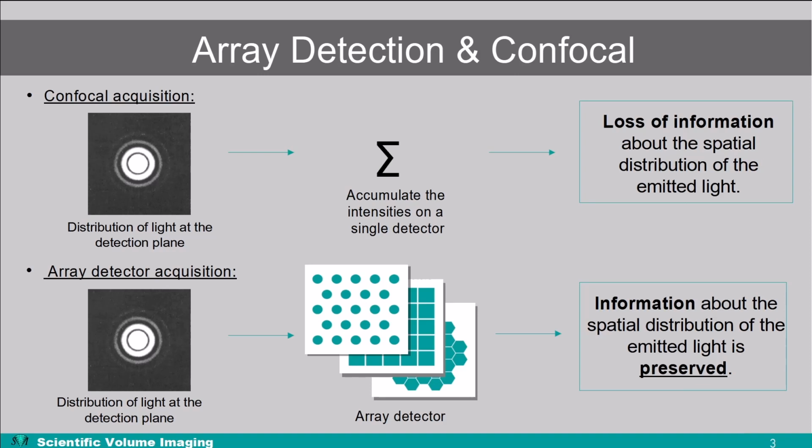However, for array detection microscopy, the light is not blocked by a pinhole. Rather, each of the separate detectors acts as a small shifted pinhole, collecting a fragment of the first Airy disk of the emission beam. Which means that each detector independently has a sharper image. However, it's less signal than a regular confocal microscope would have.